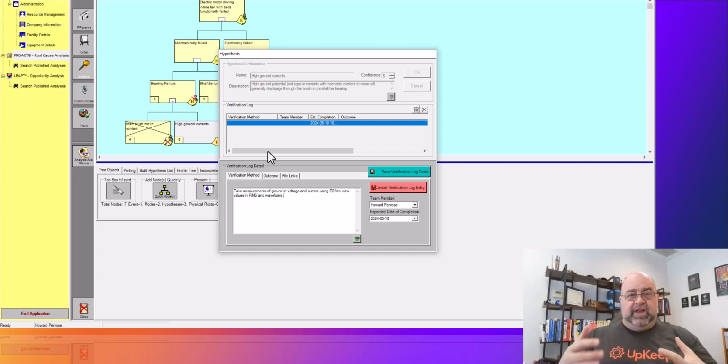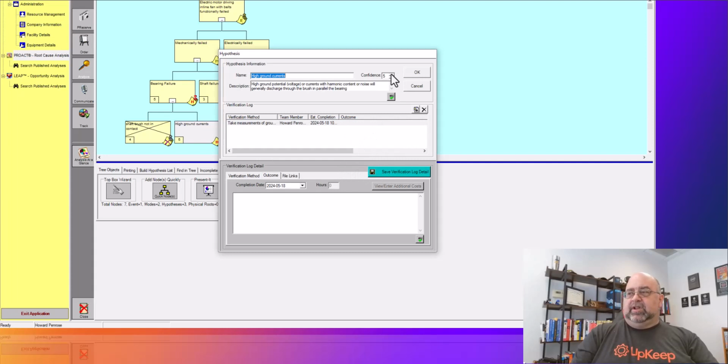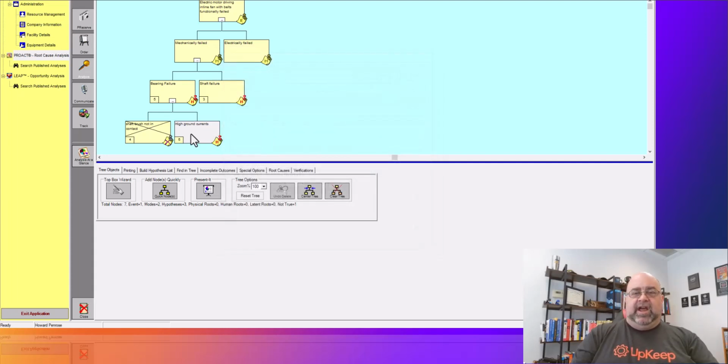We've run into this in wind, and we've run into it in other conditions. And by the way, the bearing might be on the driven component or elsewhere in the system. I'll talk about this in a few weeks, about some of what we looked at in mapping a wind turbine nacelle to detect main bearing failures. When we do that, we come to the conclusion that, because we haven't done the mapping yet, we're going to say this is a possibility, high probability, but I don't have a conclusion yet.